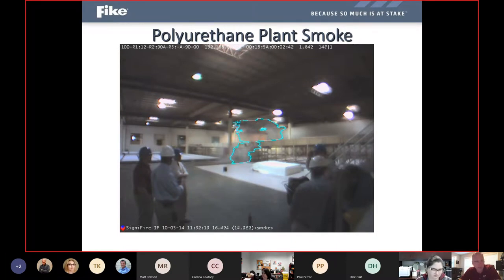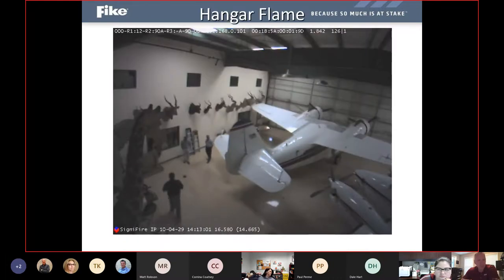in another example of its advantages, in some very high ceiling areas, that smoke may stratify halfway up or three quarters of the way up and maybe never make it all the way up to the deck. With the camera system, we don't need it to. We can track it and trace it and go into alarm regardless of how high it has risen in the area. And here's an example in a small private airplane hangar of the camera detecting flame.